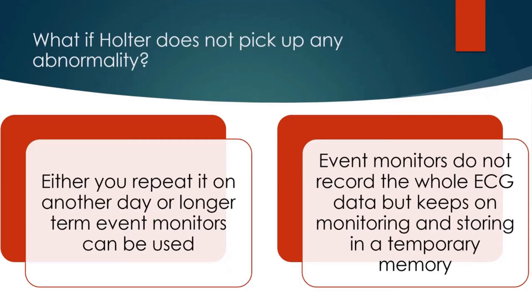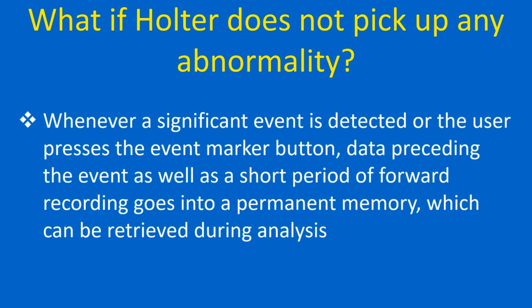What if Holter does not pick up any abnormality? Either you can repeat it on another day, or longer term event monitors can be used. Event monitors do not record the whole ECG data, but keep monitoring and storing in a temporary memory. Whenever a significant event is detected or the user presses the event marker button, data preceding the event as well as a short period of forward recording goes into permanent memory, which can be retrieved during analysis.